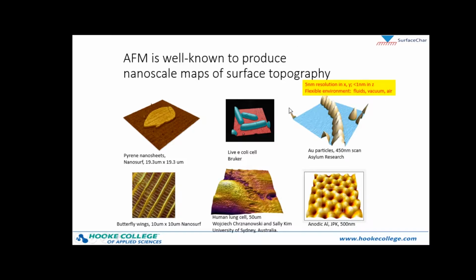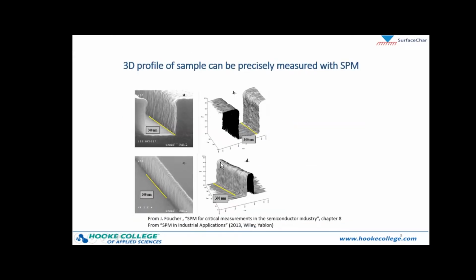And all of this imaging can be done with very high resolution. So about 5 nanometer resolution in X and Y, angstrom resolution in Z, and a flexible environment. You can image either in fluid, vacuum, or air. That's the power of AFM. And then one more word on topography. Probably one of the most common applications of using AFM for topography is in the semiconductor industry, where it's used for quality control to measure the critical dimensions of features that are important in that industry.